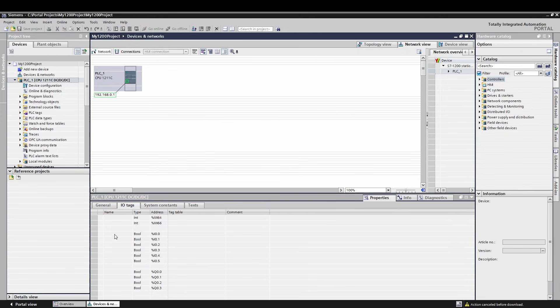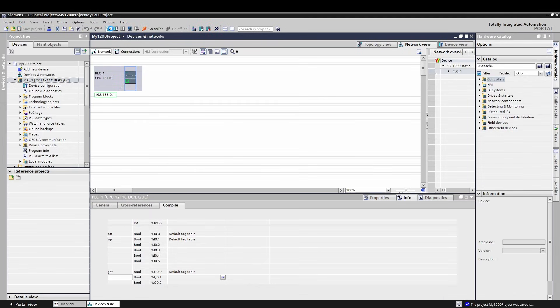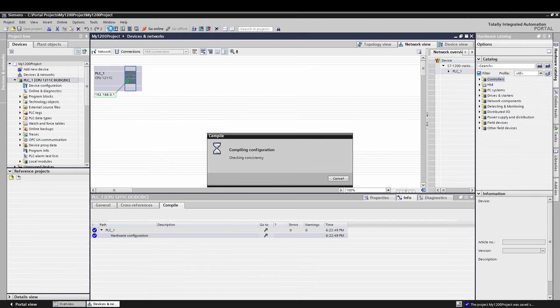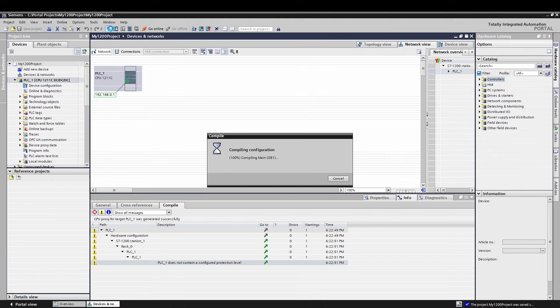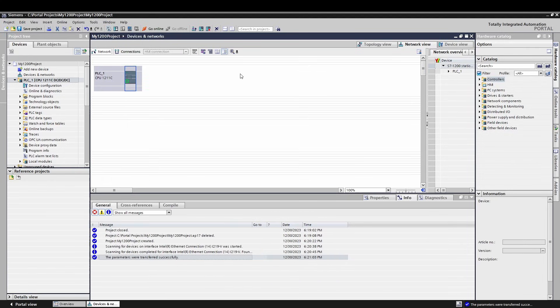Before we connect and download for the first time, let's set up a few I/O points so we don't have to come back here later. Open Devices and Networks and select our PLC. In the inspector window at the bottom, make sure you are on the Properties tab and select the I/O Tags sub-tab. Here you can quickly set up tags for the built-in I/O. We will have a start and a stop input and a light output. Let's connect and download for the first time.